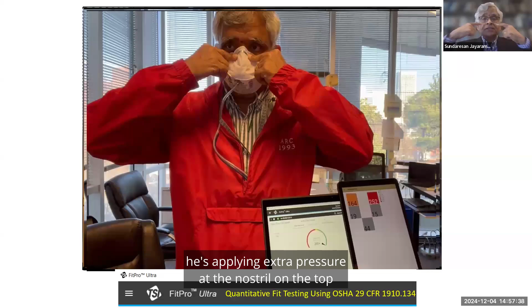So in this particular case, what the user is doing is applying extra pressure at the nostril, on the top of the nose, and therefore you're able to see that the pressure values are high. So the heat map is giving a clear indication to the user in terms of what the pressure is, and the smart algorithm that is built into it is able to detect the change in the pressure from the baseline values and is able to generate an alert. And when the user adjusts the respirator, then the seal is restored, the pressure values come back and the monitoring happens in real time.